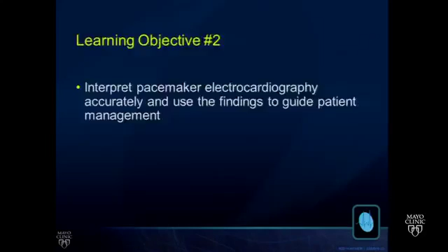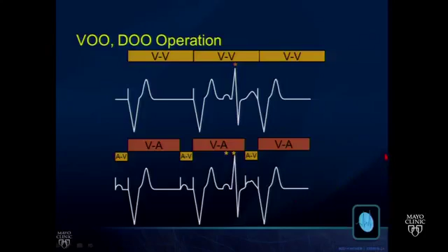Well, let's start with so-called magnet mode of operation, which in the pacemaker letter code is going to be VOO or DOO. Sensing is disabled, so the second and third letters are O. Here is a ventricular pacemaker programmed VOO, where it shows no regard for this intrinsic depolarization and paces right through at its programmed rate without any resetting of its time clock. The same idea for a dual chamber device. It paces through the recording, showing no regard for a native cardiac depolarization. So that's magnet mode, VOO, DOO pacing.